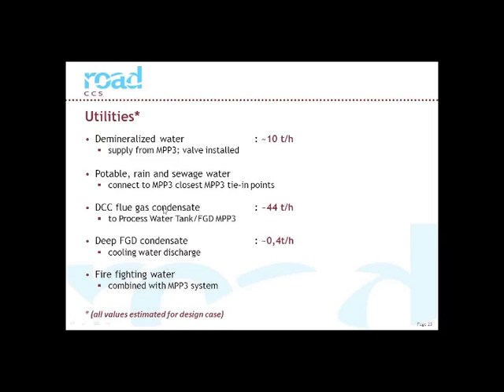One big waste stream of the capture plant is the flue gas condensate. This is almost pure water that can be used very well in the power plant for the flue gas desulfurization. So we connect it to the process water tank of MPP3. And this reduces the freshwater intake from the nearby lake significantly.